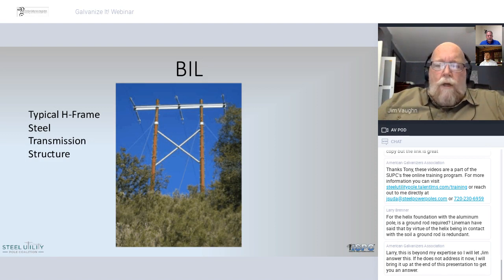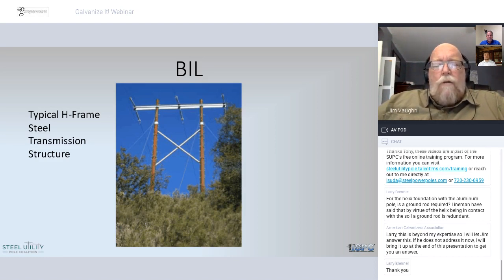So I agree with those linemen. That grid will do the job and it will put the pole to ground. But because it's considered a mechanical connection, generally engineers will also install a ground rod. The point that I was making earlier is that if the ground rod's copper and the grid is galvanized, consideration has to be made about the galvanic cell that's created when the copper is placed in the ground, or what kind of electrode to place in the ground to ensure that they don't eat each other up over the next 20 years. All right. Any other questions?